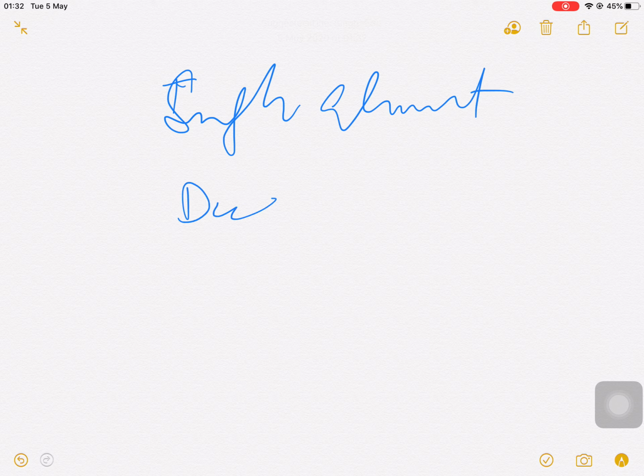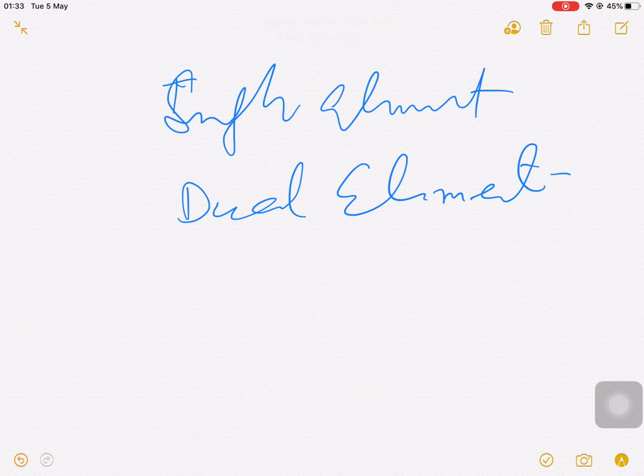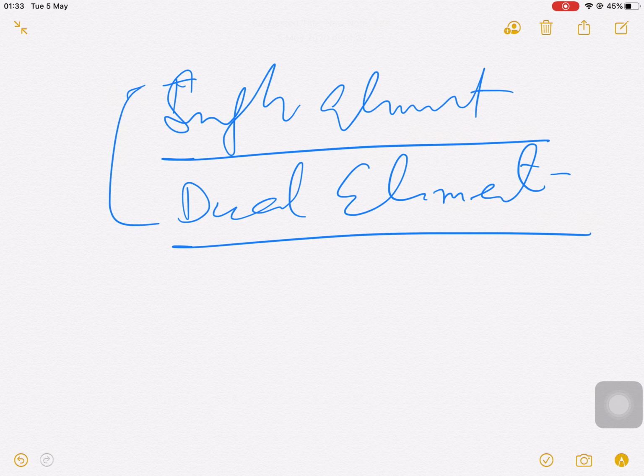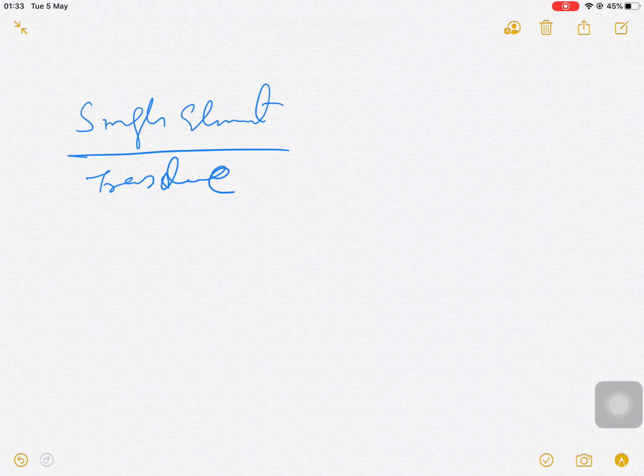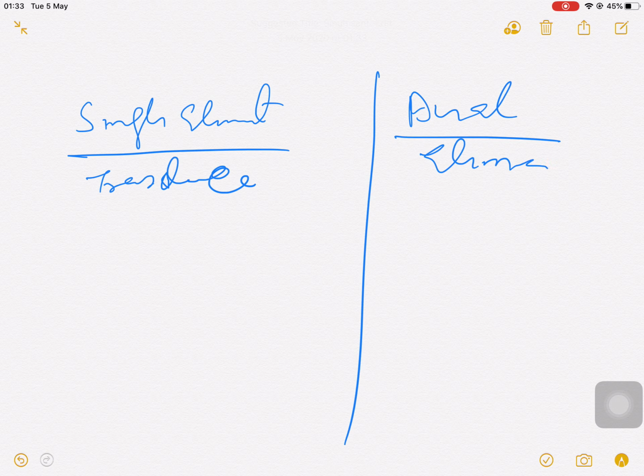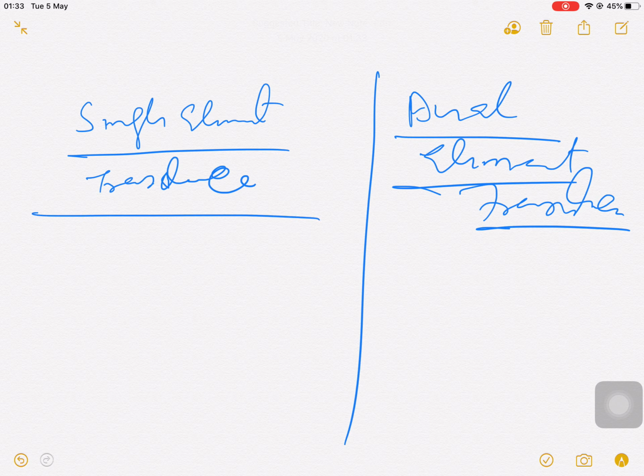So first, generally, there are typically two types: single element and dual element. First you need to understand this, single element type and dual element type. I will take you through it in full detail, how the single element transducer is manufactured, and the dual element transducer. If I tell you the single element, your probe will be like this.